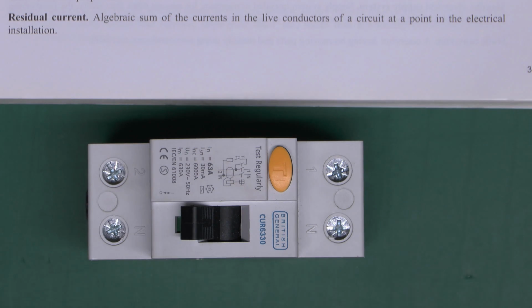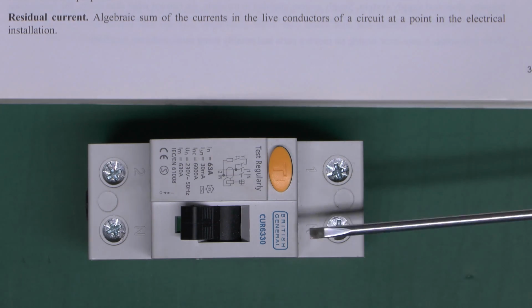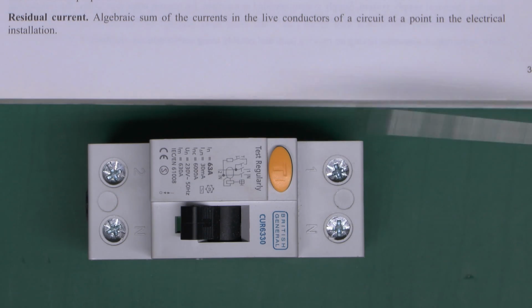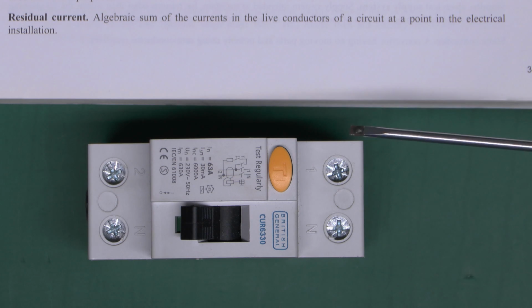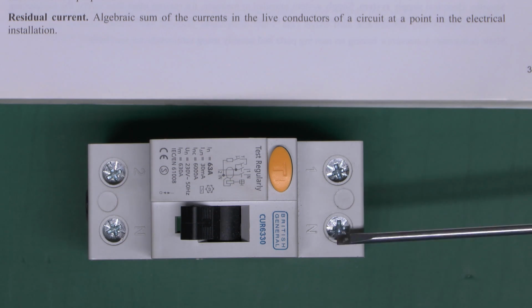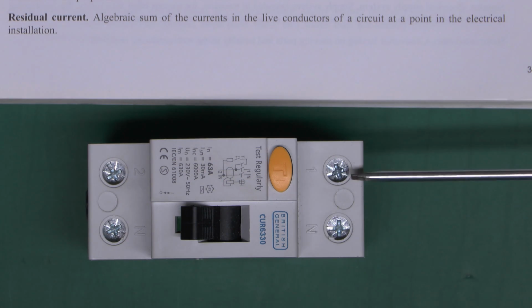However, when there's some kind of fault or other issue occurring on the load side here, some of that current is going to leak away to earth, and the return current is not going to be exactly the same as the current coming in. And this is the residual current, or what's basically left over after you've added the two together. And in this case it's a 30 milliamp device, so 0.03 amps would trip this device, and again you can get these in various other ratings. The fact that this is an AC device doesn't change anything.